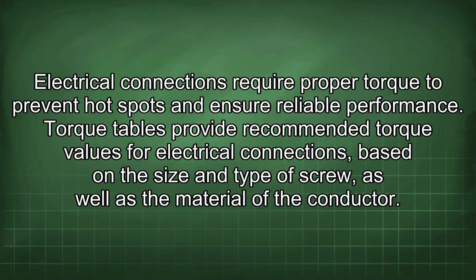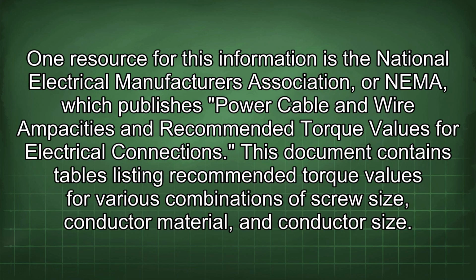Electrical connections require proper torque to prevent hot spots and ensure reliable performance. Torque tables provide recommended torque values for electrical connections based on the size and type of screw, as well as the material of the conductor. One resource for this information is the National Electrical Manufacturers Association, or NEMA, which publishes power cable and wire ampacities and recommended torque values for electrical connections. This document contains tables listing recommended torque values for various combinations of screw size, conductor material, and conductor size.